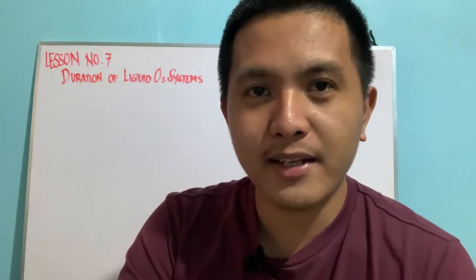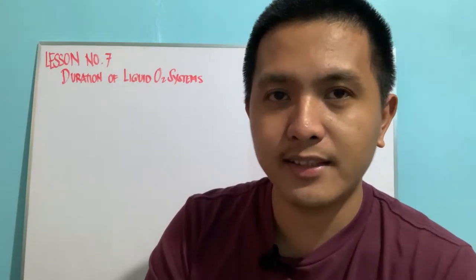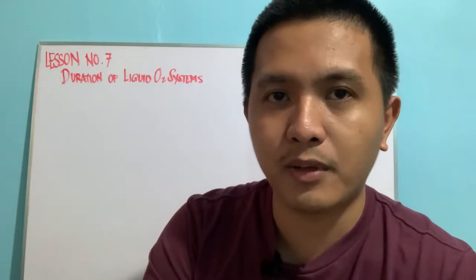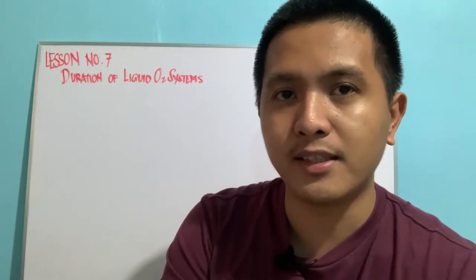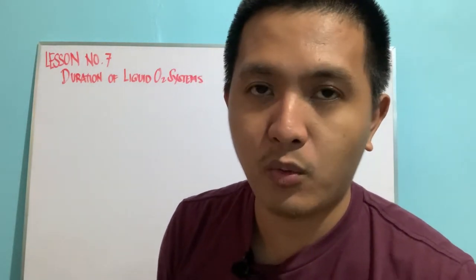Welcome back to At Your Service. This is lesson number seven: how to compute for the duration of a liquid oxygen system. Liquid oxygen systems are used to provide bulk oxygen supply to patients who require long-term oxygen. Liquid oxygen is measured by its weight because we cannot measure its pressure.